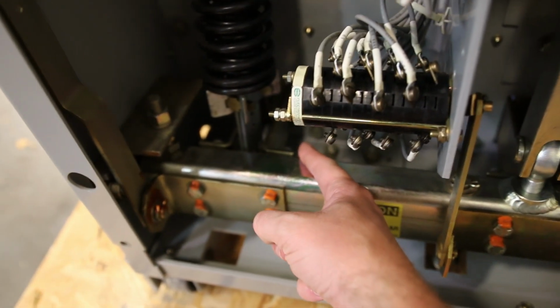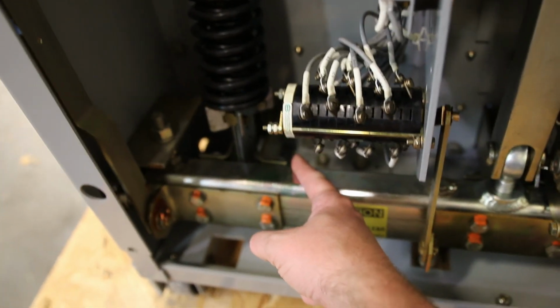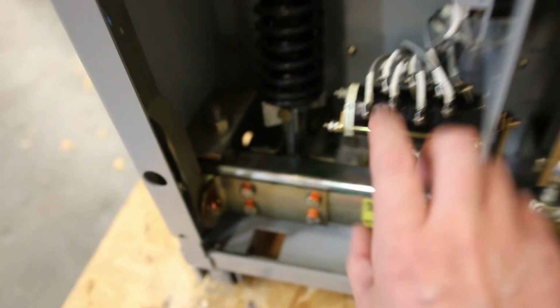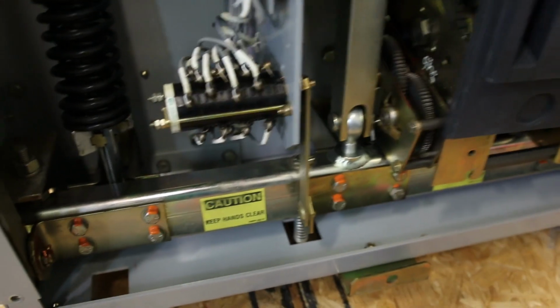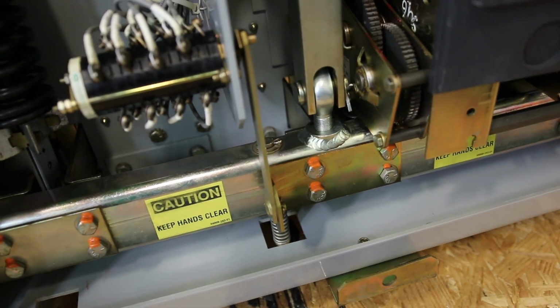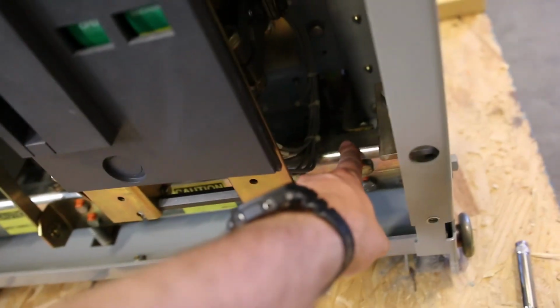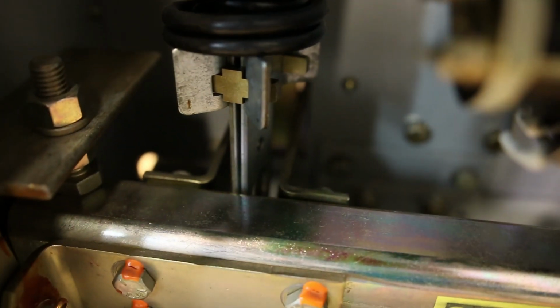So if we can see these little, focus, there we go. If we see these little bars coming out the bottom off of this bar will rock back and forth, and that's all the motion that it takes to open and close the contacts on the breaker. So we've got our A phase is actually over here. See if I can get this in focus here. There we go. So it's actually two little bars that come off this main drive rod here.